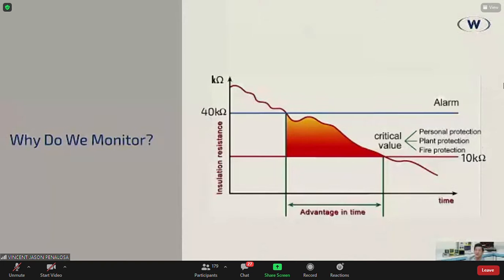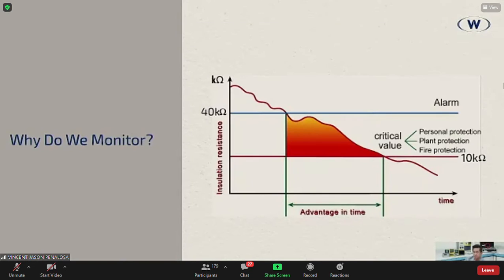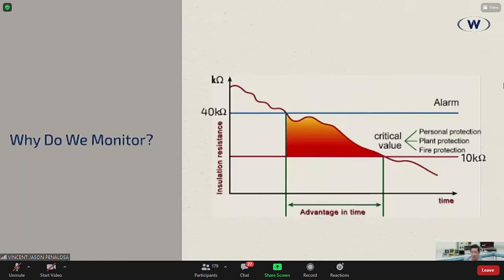So why do we monitor in the first place? Why do we monitor in the first place? Now, of course, you want to make sure that personal protection, plant protection, and fire protection is not compromised. Now, the regular insulation monitoring device, right out of the box, will make its first alarm at 40 kilo ohms. And the critical alarm based on IEC is set at 10 kilo ohms.